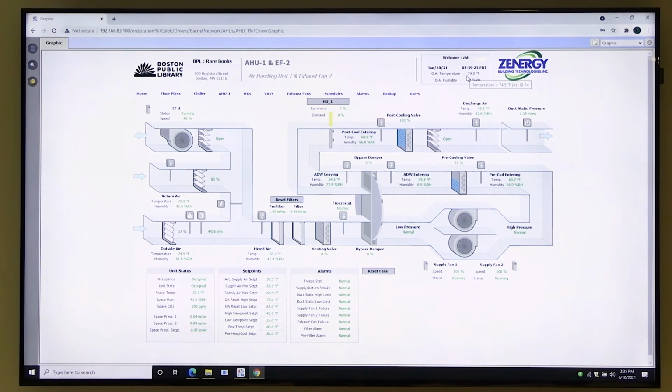I see what you mean though with the humidity. I'll double check that. You should see those match. I see what you're saying here. Yeah, we're not actually using this to control anything. The humidity outside, it's really just the outside air temperature that is the important one for this. But yeah, it's important that it makes sense.